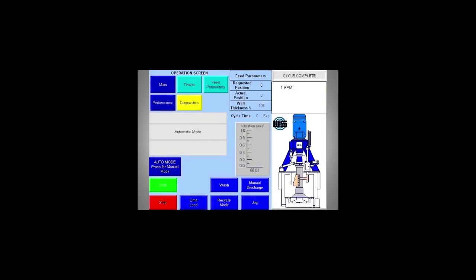The operation screen is the primary screen for running the centrifuge. From here, you can return to the main menu, adjust timers, set feed parameters, and look at performance and diagnostics information. Additional details displayed on the operation screen include feed parameters, cycle time, vibration level, RPMs, and the machine cycle.